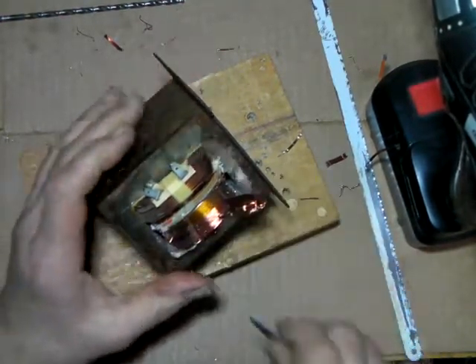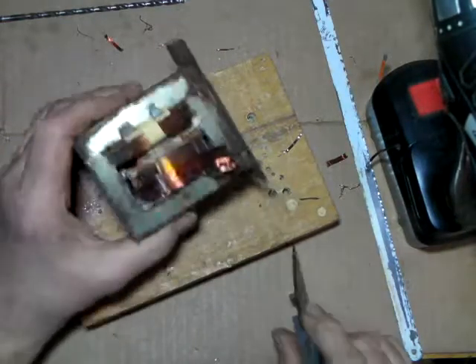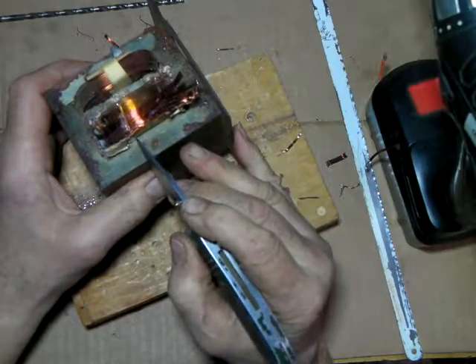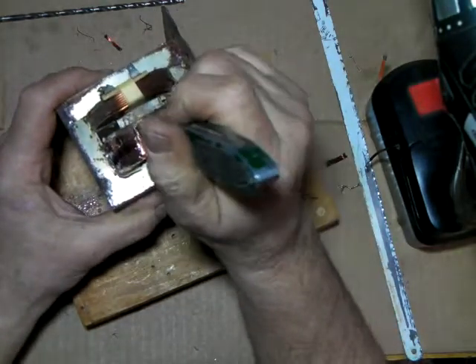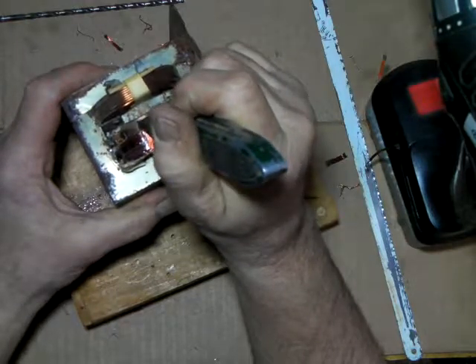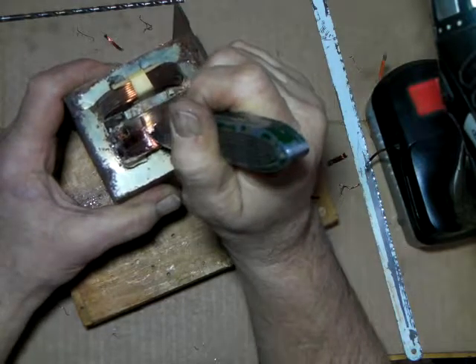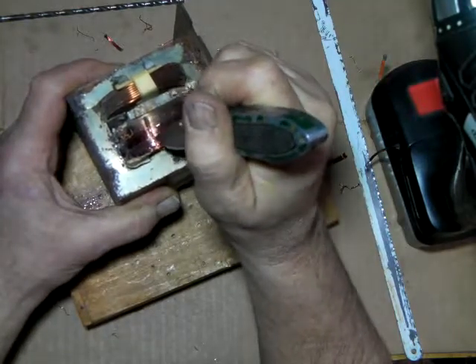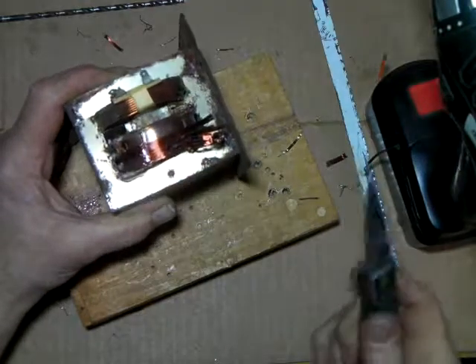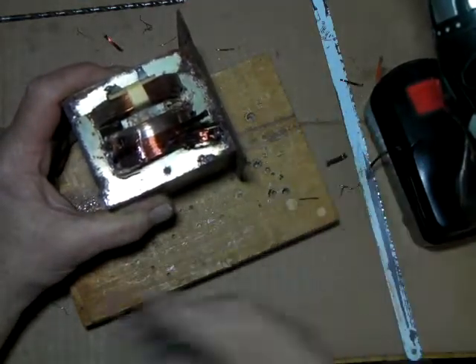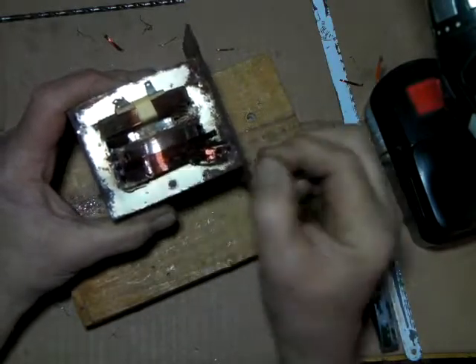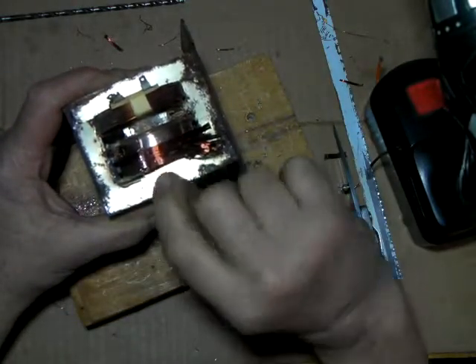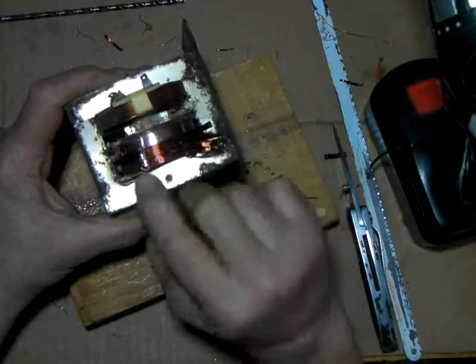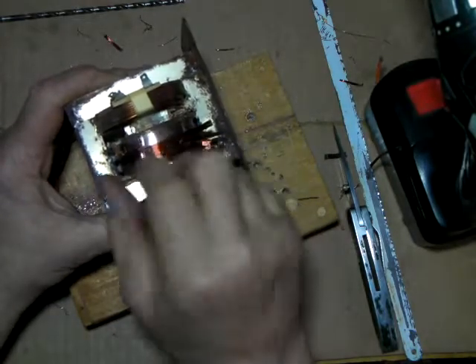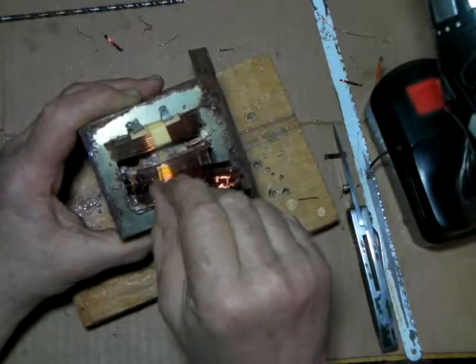Now when you're coming down with your knife, don't cut too far down on the sides. You want to just stay on this face and come across. Basically what you're trying to do is take the first, second, third layer - maybe it'll take 2 or 3 layers at a time that you're going to cut through, and that's okay. Keep dewinding this until you've started running out of wire that you can pull off. In other words, you'll go around the transformer, and when you come to this cut, it'll break off. You keep going until you've cleaned that up and you're down to where you've got maybe 1 or 2 wires that you can grab.